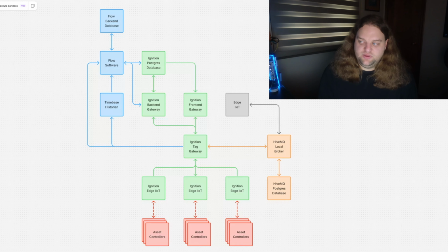Typically speaking, I try to map that as one-to-one as possible in the UDT structure. So anytime you have a nested object in your JSON payload, I'll have a nested UDT in Ignition. And once you have that data model figured out and standardized, it's pretty easy to make UDTs in Ignition that map one-to-one to those JSON objects. The rule of thumb there is that anytime you have a nested object or array in the JSON, that usually represents itself pretty well as a nested UDT, or a nested structure of UDTs under parent UDTs.